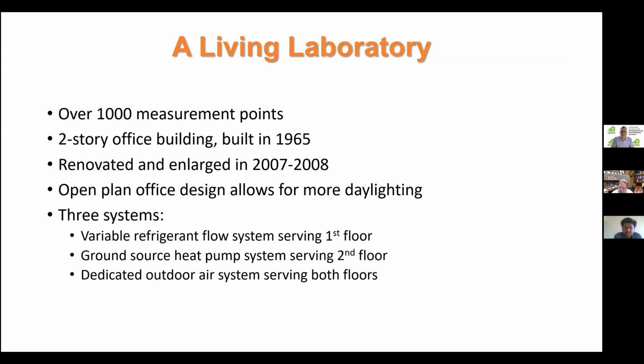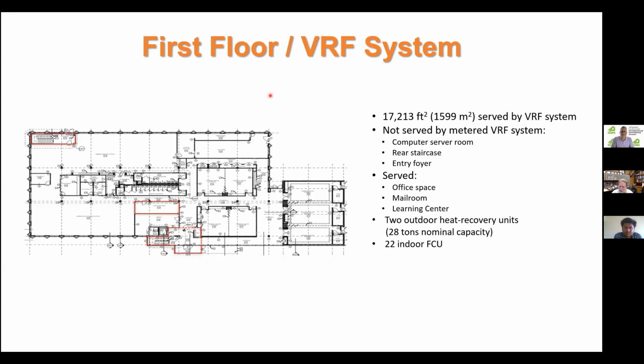They changed some things. It changed to an open plan office design to have more daylighting. But really from my view, the main innovation was in the system. So they had a variable refrigerant flow system serving the first floor of the building, a ground source heat pump system serving the second floor, and then also a dedicated outdoor air system. And the VRF system served about 17,000 square feet. There were a few areas on the first floor it didn't serve. Mainly it was office space, mailroom, and the learning center, which is only used some of the time. But I think the learning center can hold over 100 people, so they had some meetings there, but infrequently used. Had 2 outdoor units, 28-ton nominal capacity, and 22 indoor fan coil units.